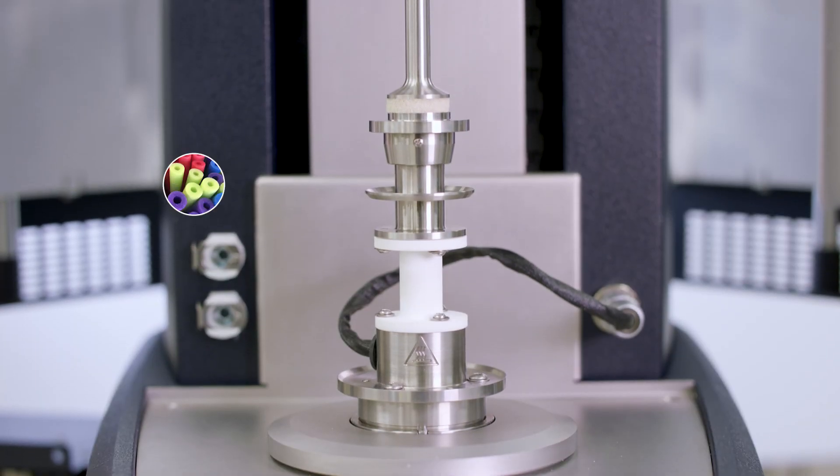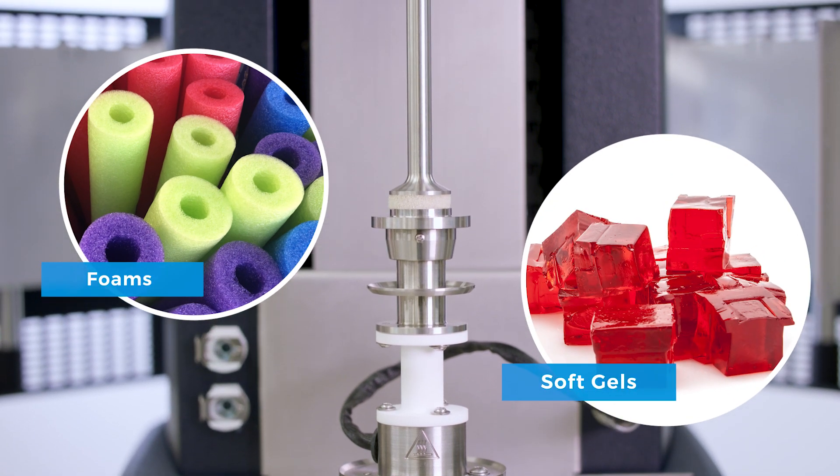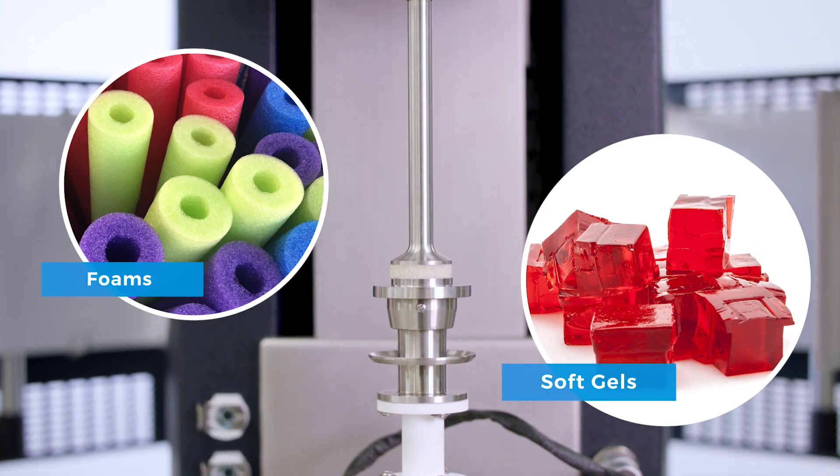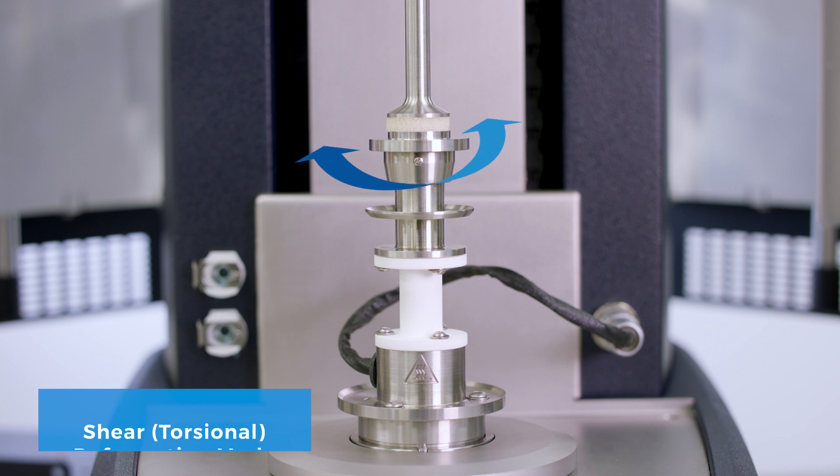Finally, materials like foams or soft gels can be tested using the parallel plate geometry. With the parallel plate geometry, sample can be tested under the regular shear deformation mode. Using the Discovery Hybrid Rheometer equipped with the axial DMA capabilities, the same parallel plate geometry can also be used to test soft samples under compressive deformation as well.